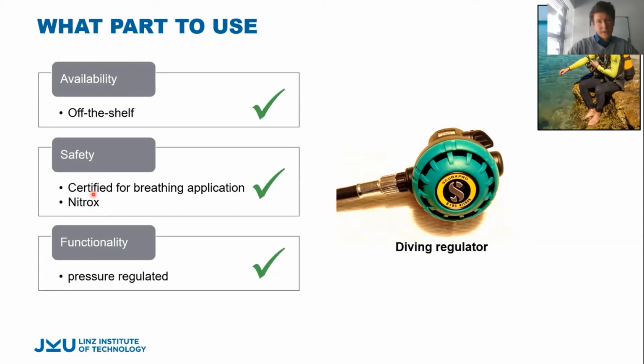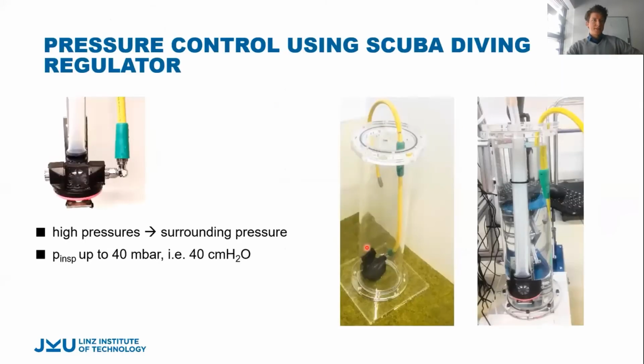And in the European Union, there's a regulation that whenever some component uses oxygen-enriched air, then it must also be safe for 100% oxygen. So this is also checked. And of course, it has the functionality. It is a pressure regulator and nothing else. So how would this work? This is the scuba diving regulator. It takes high pressure, like 10 bars or so, and by a valve transforms it into a surrounding pressure. So basically down here, there's a membrane, and this membrane actuates the valve and does this trick. So we actually need here inspiratory pressure up to 40 millibars.